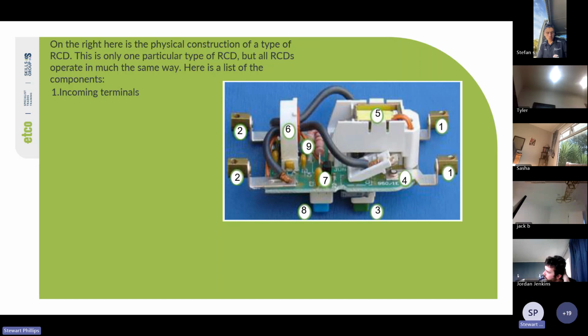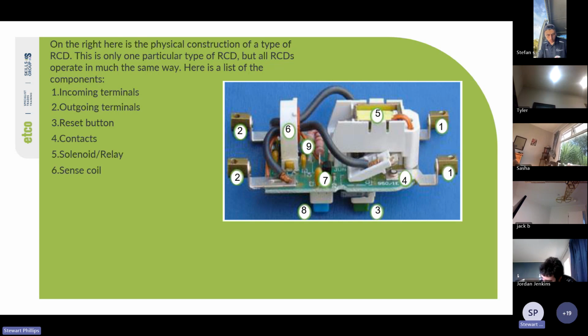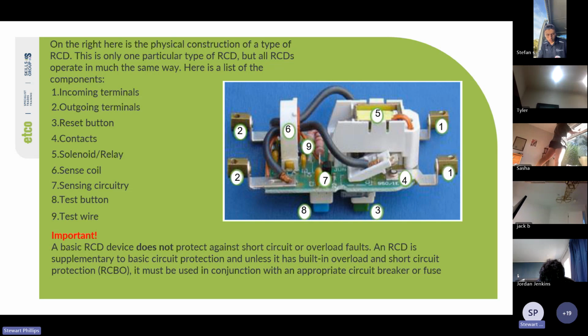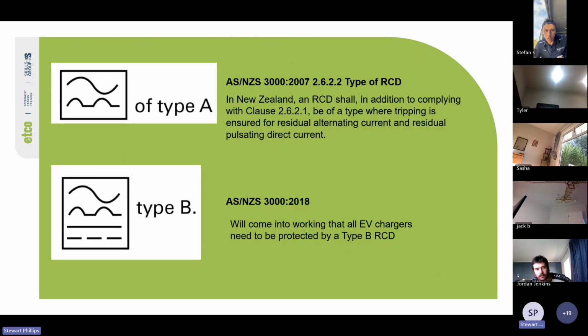So if we look at the RCD, you've got the different parts. The list of components: you've got the incoming terminals on one side, the outgoing terminals on the other. You've got a reset button. You've got contacts, a solenoid relay, sense coil, your sensing circuit, a test button, a test wire. But important, the basic RCD does not protect against short circuit or overload faults. An RCD is supplementary to basic circuit protection unless it has built-in overload and short circuit protection, or is an RCBO. It must be used in conjunction with an appropriate circuit breaker or fuse.